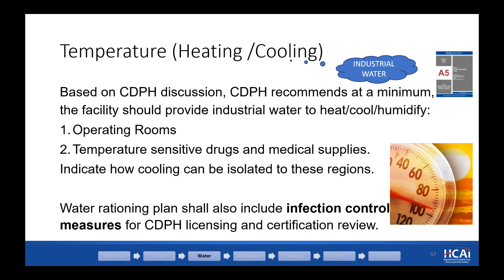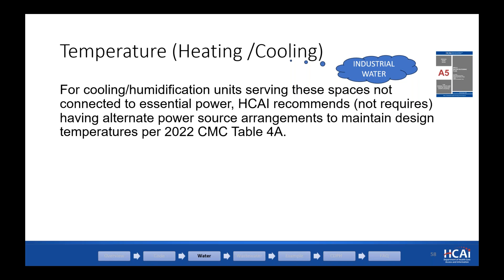For cooling and humidification units serving these spaces not connected to essential power, HCAI recommends, not requires, having alternate power source arrangements to maintain design temperatures per the California Mechanical Code Table 4A. Again, it's our understanding that the code requires e-power for ventilation and heating, but not for cooling or humidification. Some facilities have a certain portion or all of their units on e-power as a good practice, but not all facilities, unfortunately. Again, we want to emphasize we are only recommending having an alternate power source arrangement. We are not requiring it.